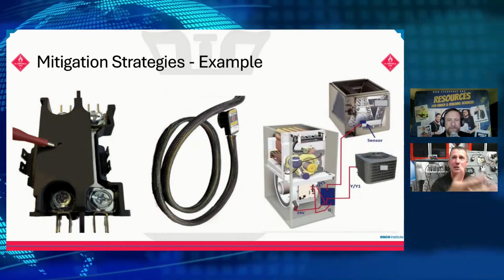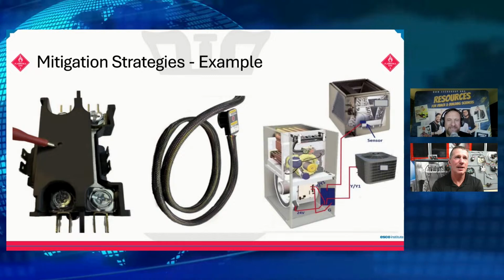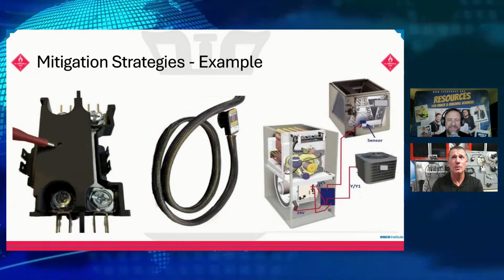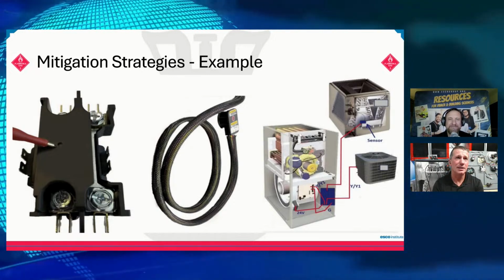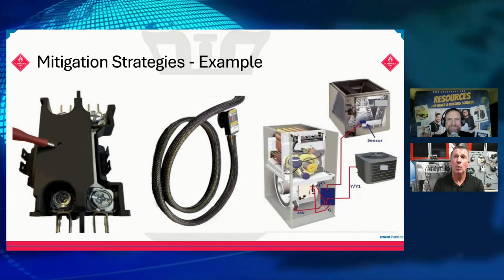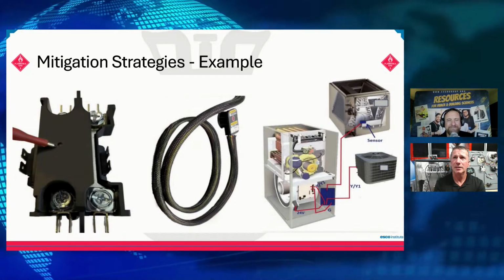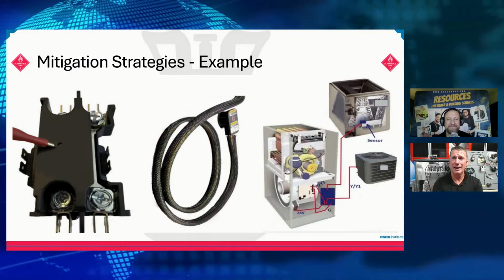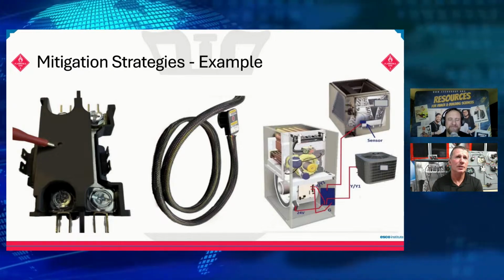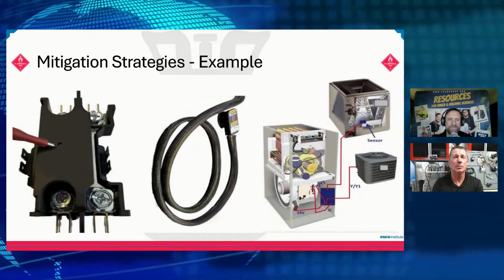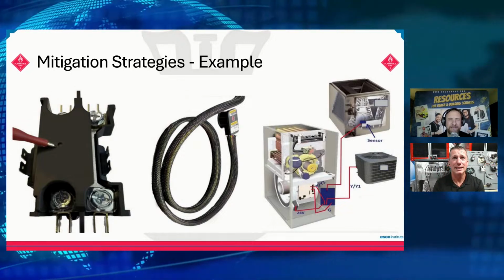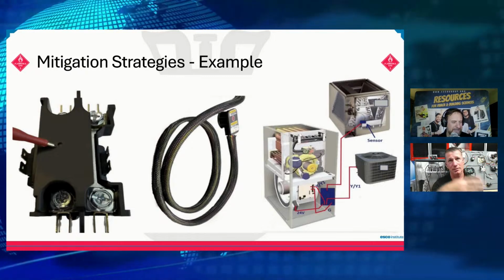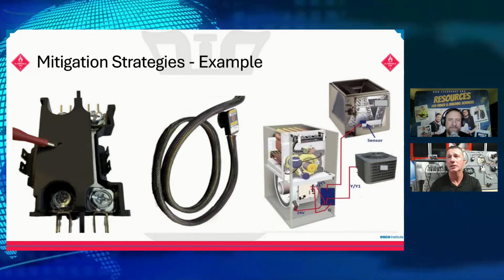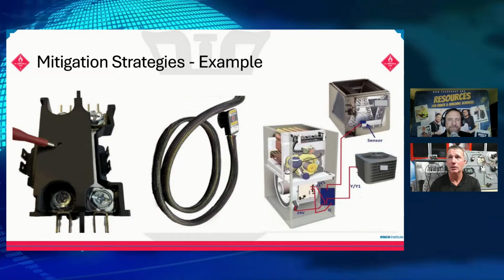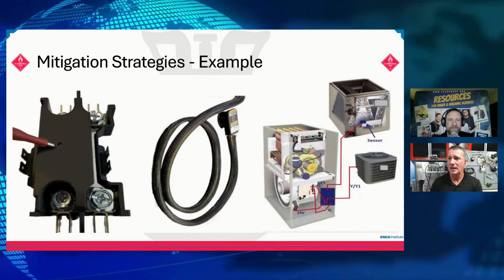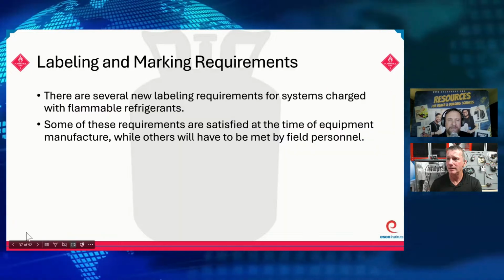You'll start seeing a few changes on our outdoor units, but not much. If we haven't already seen a contactor with a cover, they've been out for a long time with quite a few manufacturers, so we'll start seeing covered contactors. We'll likely see other heavier concealed controls, especially with air handlers and heating element controls. We'll also see solid molded plugs with retaining clips on compressors if they didn't already have them. Our major manufacturer of many scroll compressors has been doing that for a long time, so that's a potential change we'll see on some equipment.